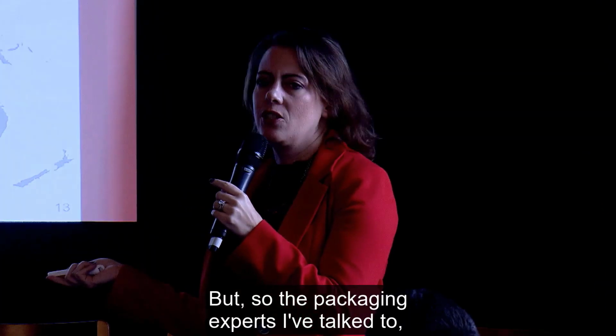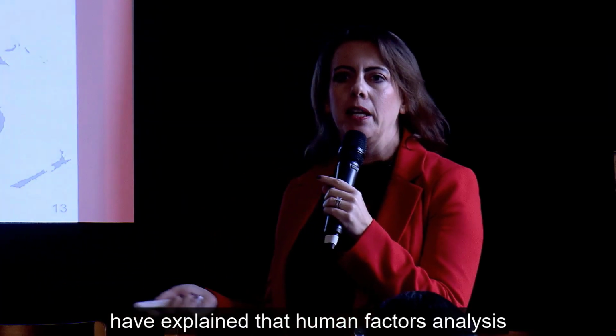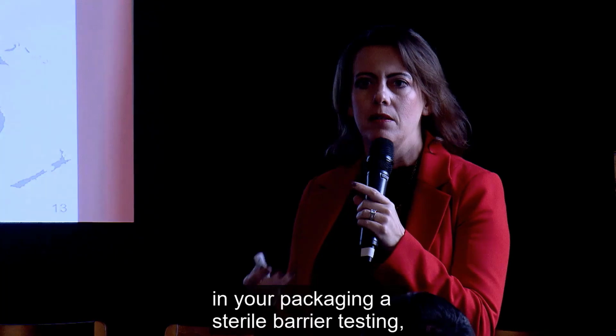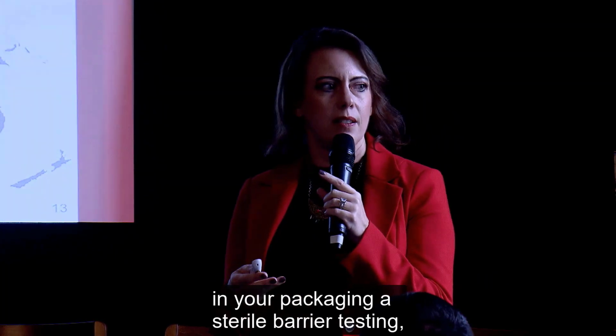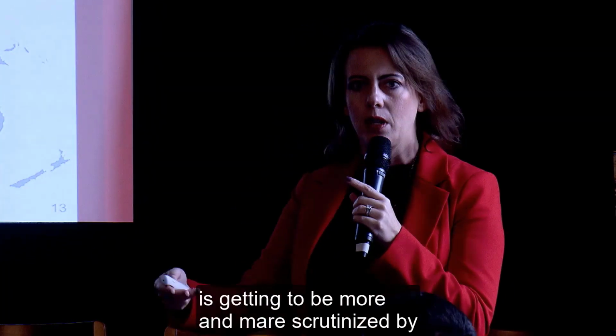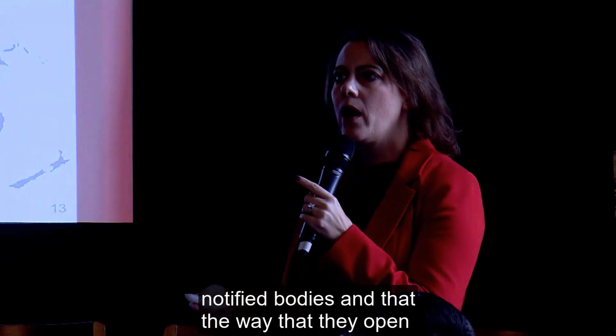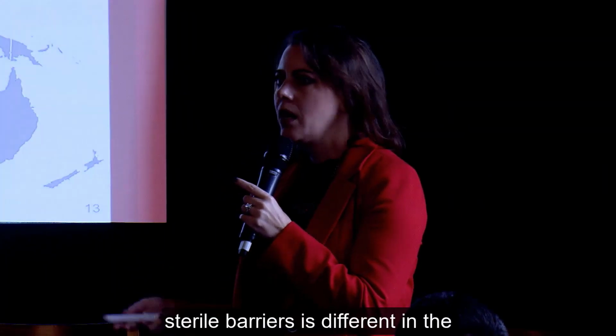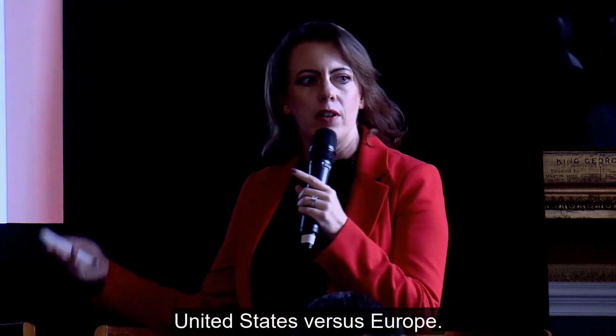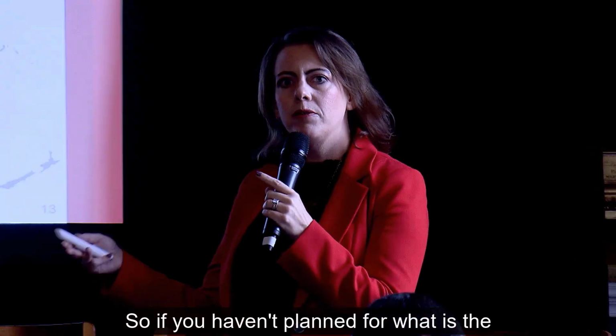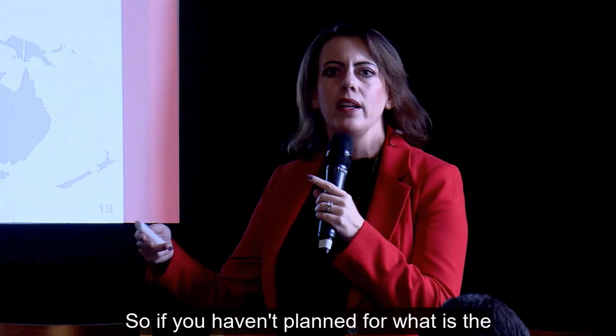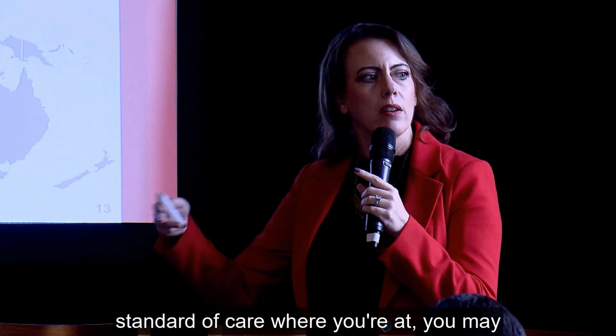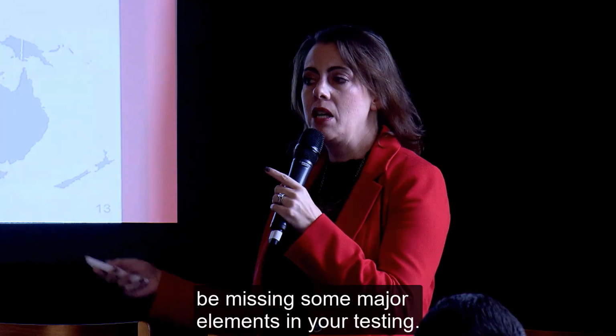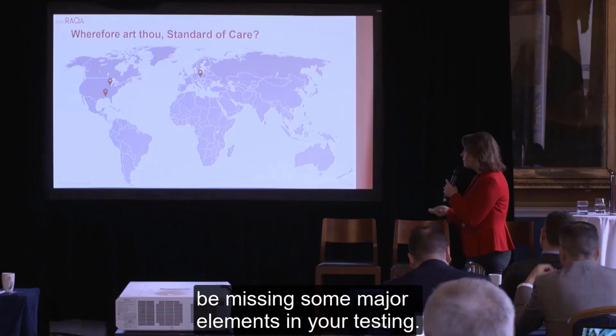So the packaging experts I've talked to have explained that human factors analysis in your packaging and sterile barrier testing is getting to be more and more scrutinized by notified bodies, and that the way that they open sterile barriers is different in the United States versus Europe. So if you haven't planned for what is the standard of care where you're at, you may be missing some major elements in your testing.